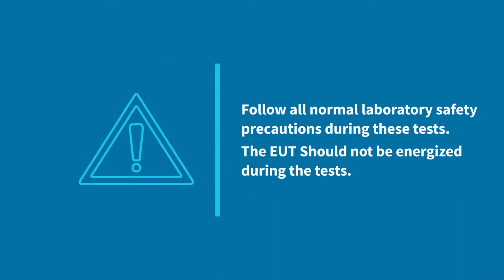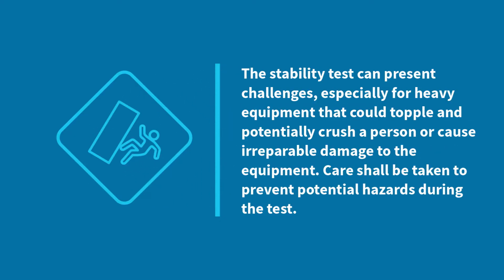Safety precautions. Follow all normal laboratory safety precautions during these tests. The EUT should not be energized during the tests. The stability test can present challenges, especially for heavy equipment that could topple and potentially crush a person or cause irreparable damage to the equipment. Care shall be taken to prevent potential hazards during the test.